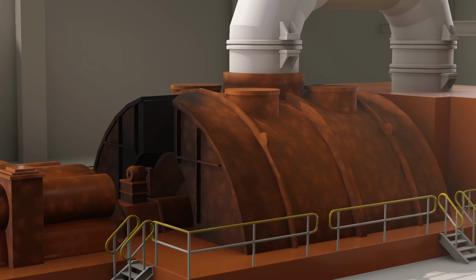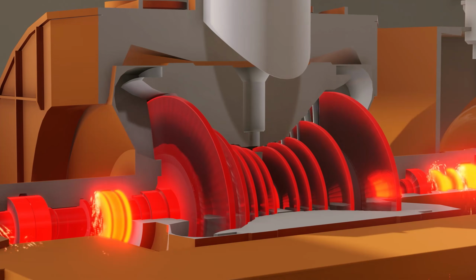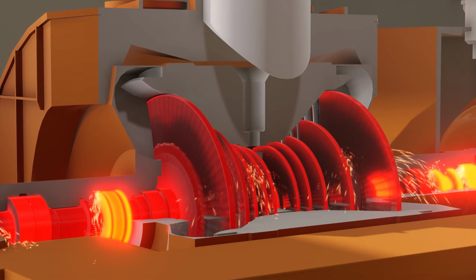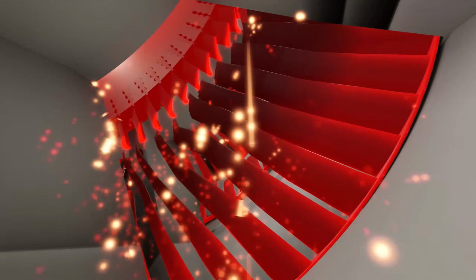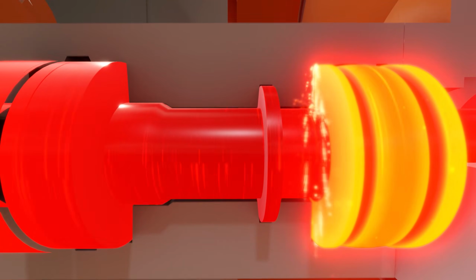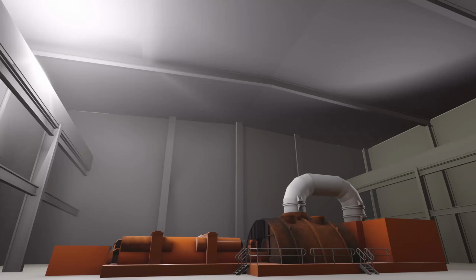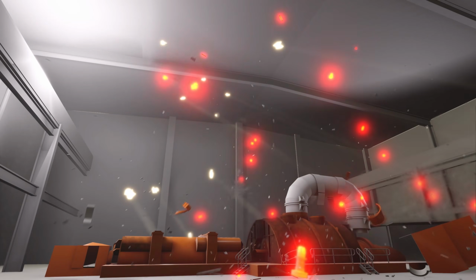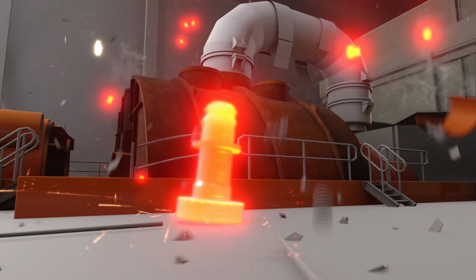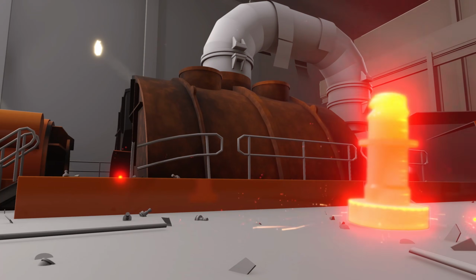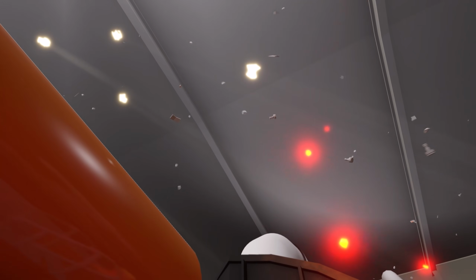At 2:06 p.m, the excessive wear on the shaft causes the turbine blades to catch on the casing, and the shaft tears itself apart at 9 locations, ejecting chunks of shaft from the generator unit. A piece weighing more than 2,000 kilograms is thrown 5 meters across the ground like a spinning top. The barring gear weighing 300 kilograms is launched 20 meters into the air, punching through the turbine hall roof.